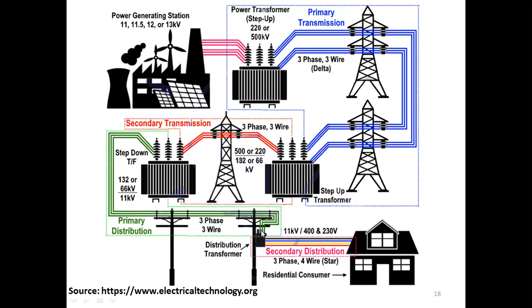See, in our street you could see a transformer between two poles. It is mounted on the pole post. That is called a distribution transformer. The incoming voltage of the distribution transformer is 11 kV. The output is 400 volt line voltage, but if you are a single phase user, then it would be 230 volt. That line is given to your home.